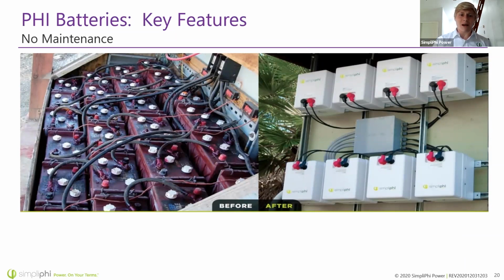Additionally, we've cleaned up this mess of wiring. You see a lot of corrosion here. Maybe even this battery looks like it's gotten too hot and melted the case, I'm not sure. And I believe these here are temperature sensors, so that the charger can temperature compensate the batteries. That's not needed on our batteries. Actually, it's not recommended at all. So it makes wiring a lot easier to not have to worry about those.